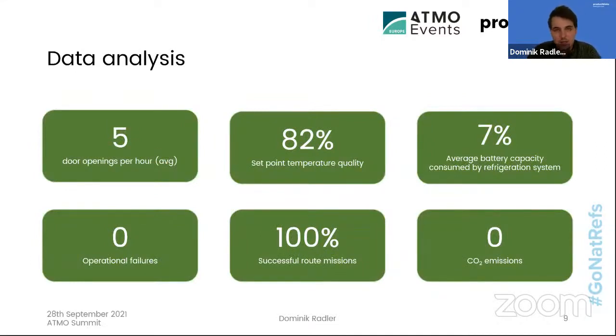In the field test case with fine delivery of parcels, of bio or organic food parcels, we had about 5 door openings per hour. Even with this, we had a set point quality of 82%, meaning 82% of the time, even during or immediately after these door opening phases, the set point stayed within the acceptable tolerance of plus minus 0.5 degrees C. The set point was 4 degrees C, with an acceptable margin of 3.5 to 4.5 degrees C.